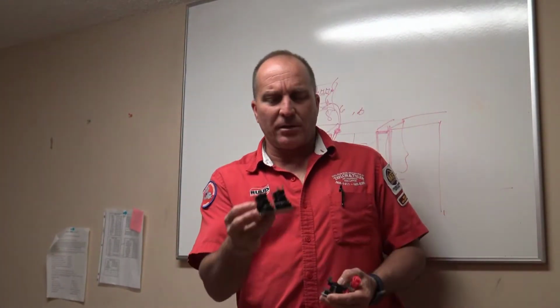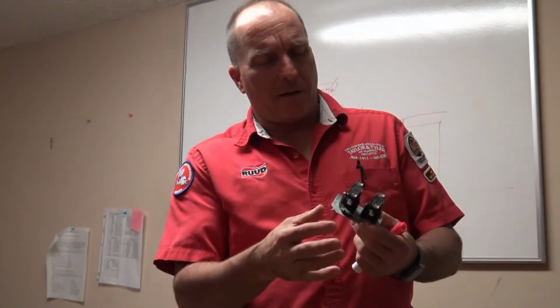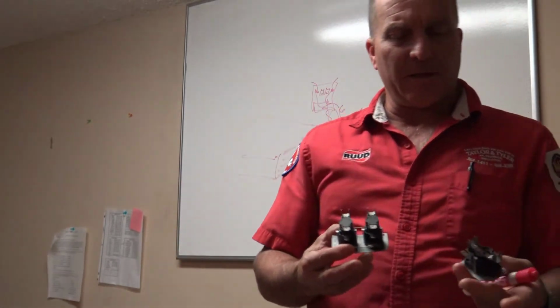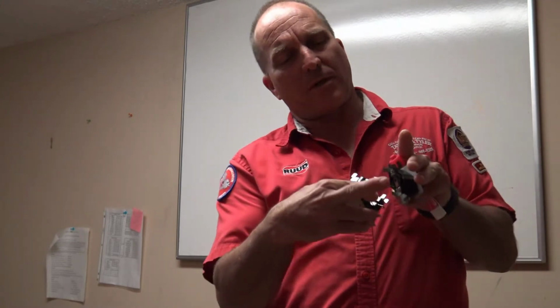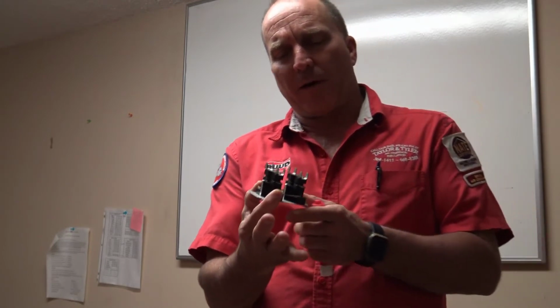This is a heat sequencer. This is a double heat sequencer, as you can see. This would be a single one. This one here is broken. The top is broken on it. So you would supply voltage to this side and this side for low voltage, your W, your common, to here.